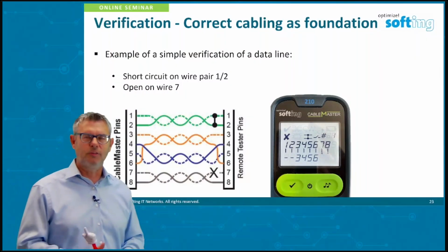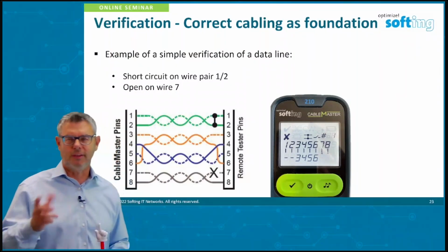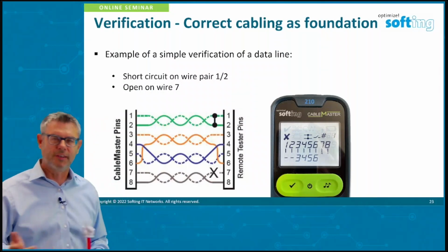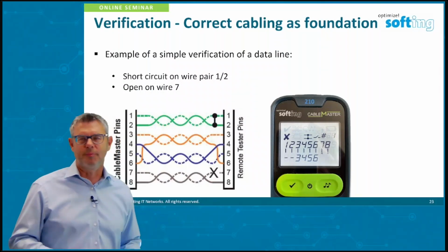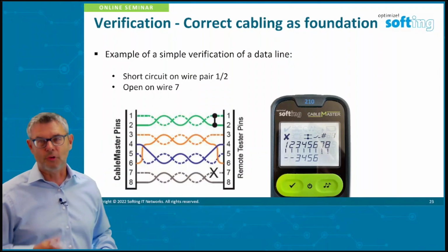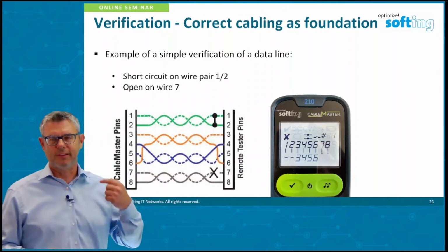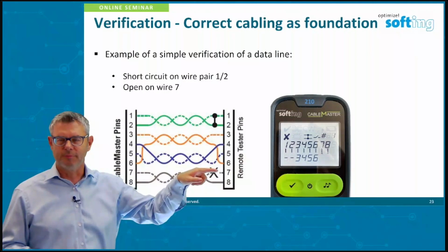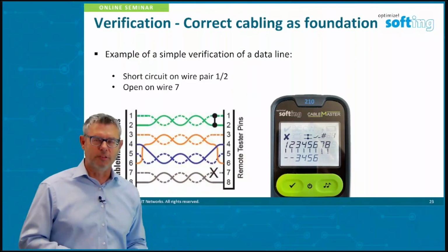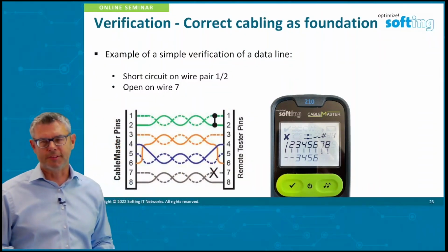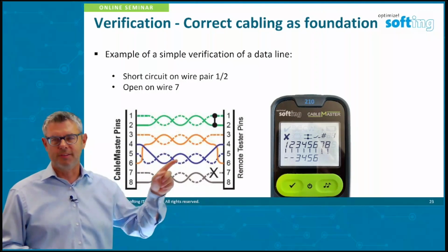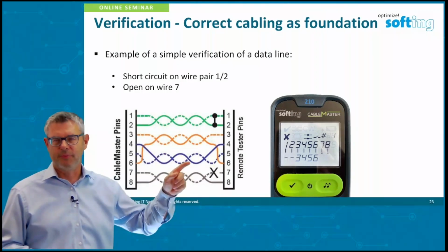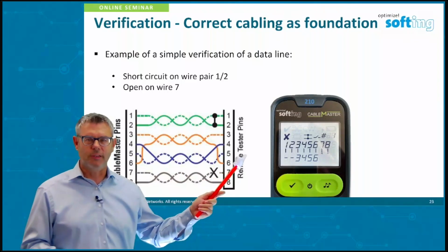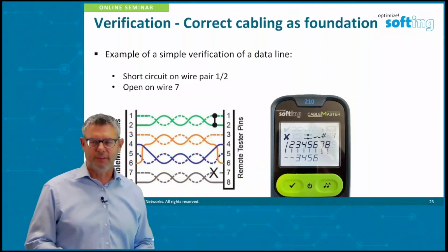When you're lucky, opening one side of your link, you find the two faults in one link. Great, lucky. If it comes to a worse situation, you see on one side it's a short and the other side is an open. Not good. Or if it comes to the really worst case, one of these problems is somewhere in the middle. These small testers in the very low range can't tell you where it is.